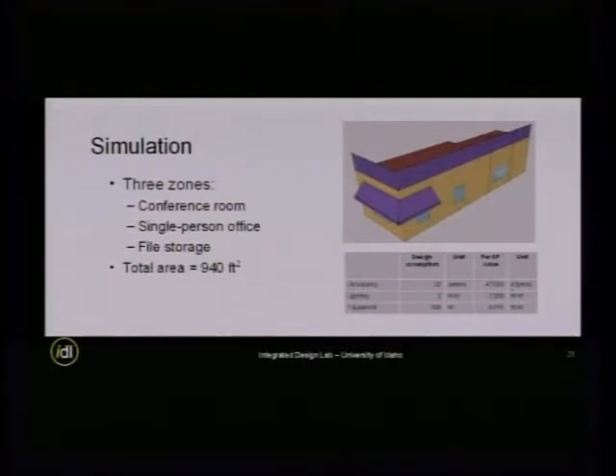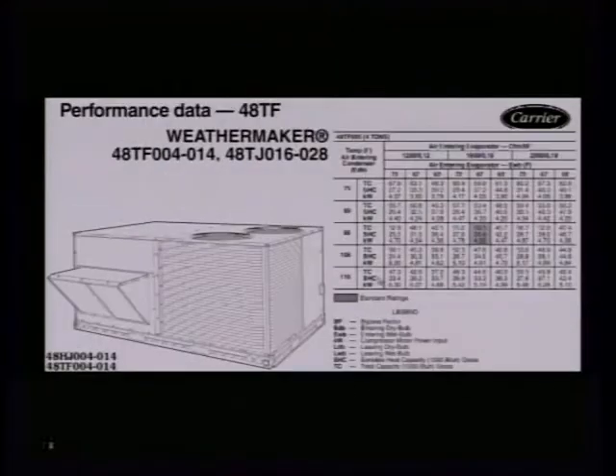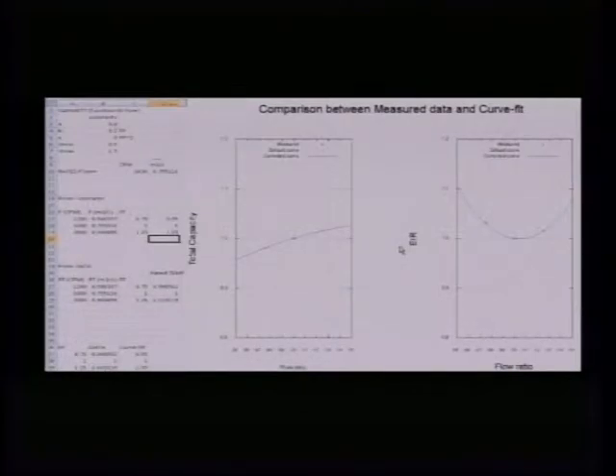A small building, three rooms: a conference room, a one-person office, and a file room, a file storage, with a total of 940 square feet. And these are the design assumptions, as in the design calculation. So what I did is, this is the unit in there. So we have this performance data of the air conditioning unit, and we also developed a custom performance curve to be used for the simulation.